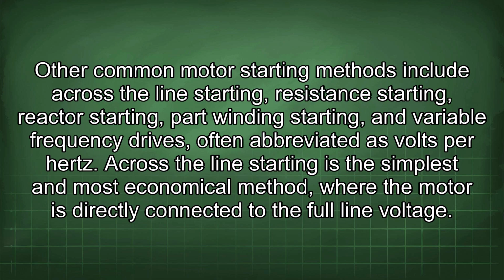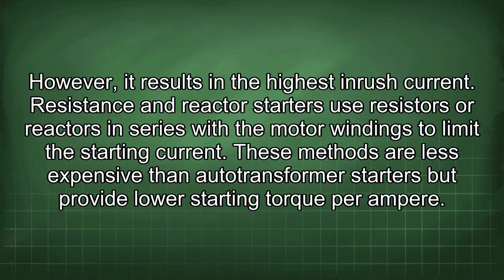Other common motor starting methods include across-the-line starting, resistance starting, reactor starting, part winding starting, and variable frequency drives, often abbreviated as volts per hertz. Across-the-line starting is the simplest and most economical method, where the motor is directly connected to the full line voltage. However, it results in the highest inrush current.